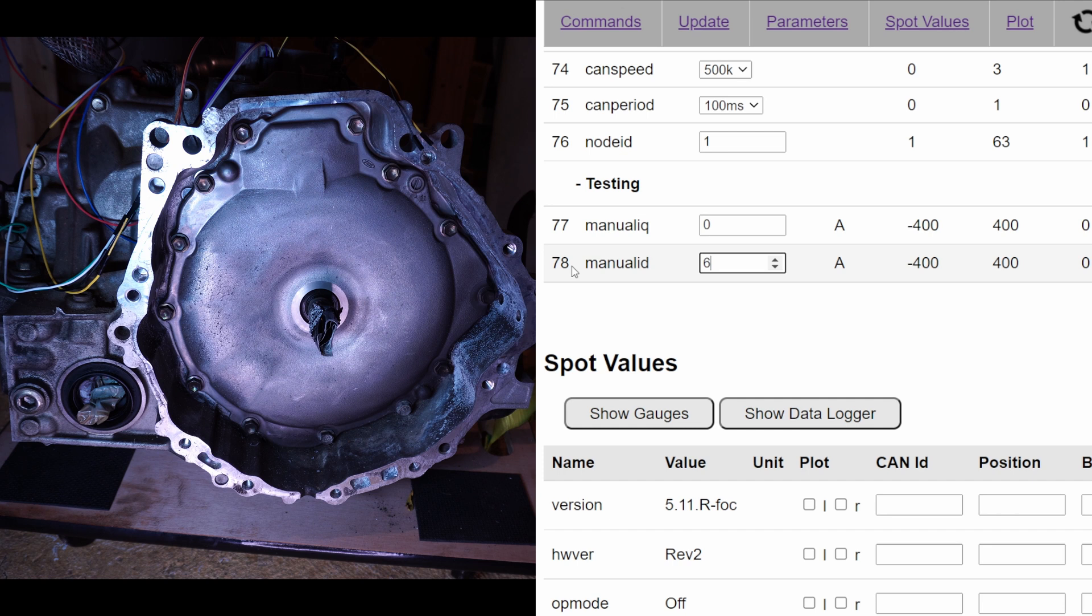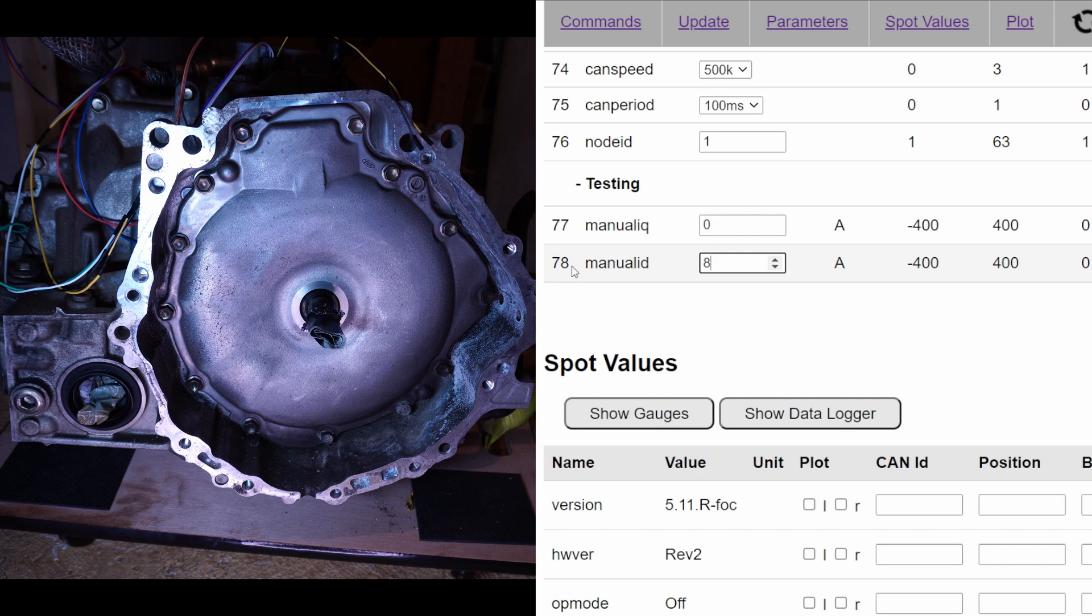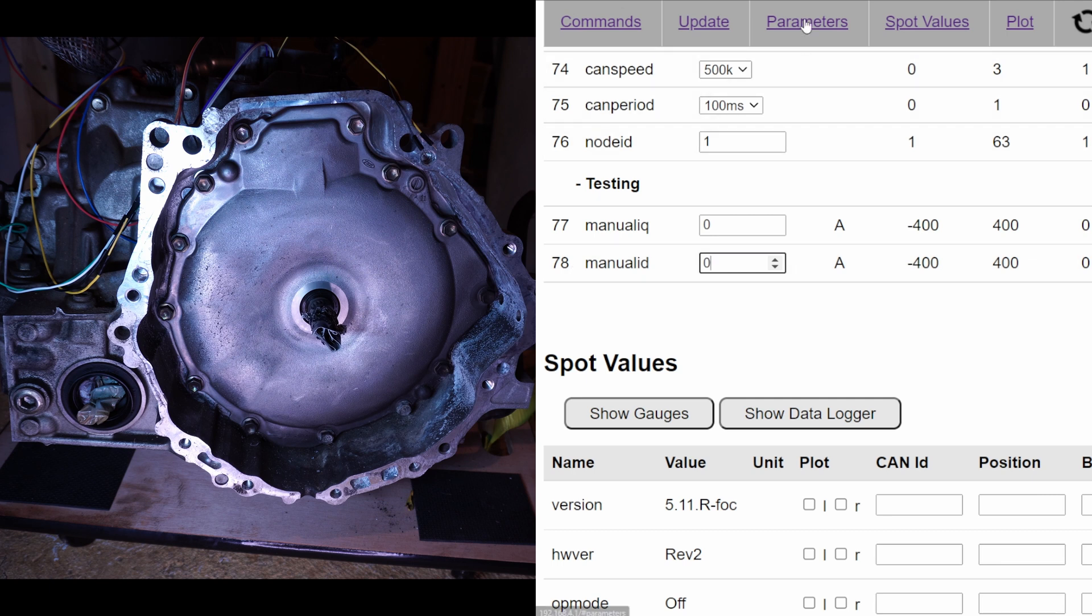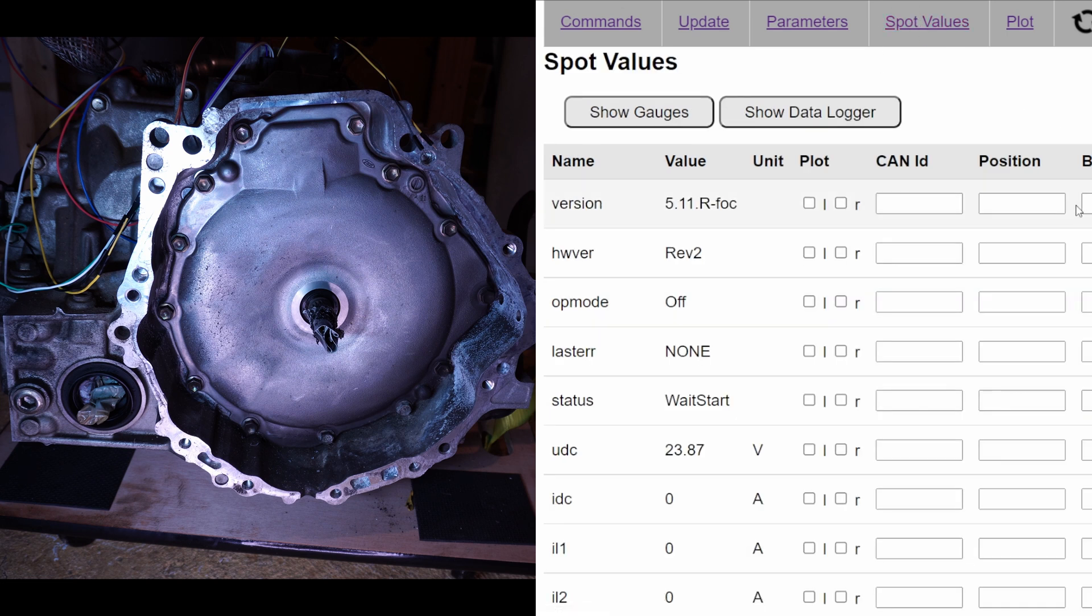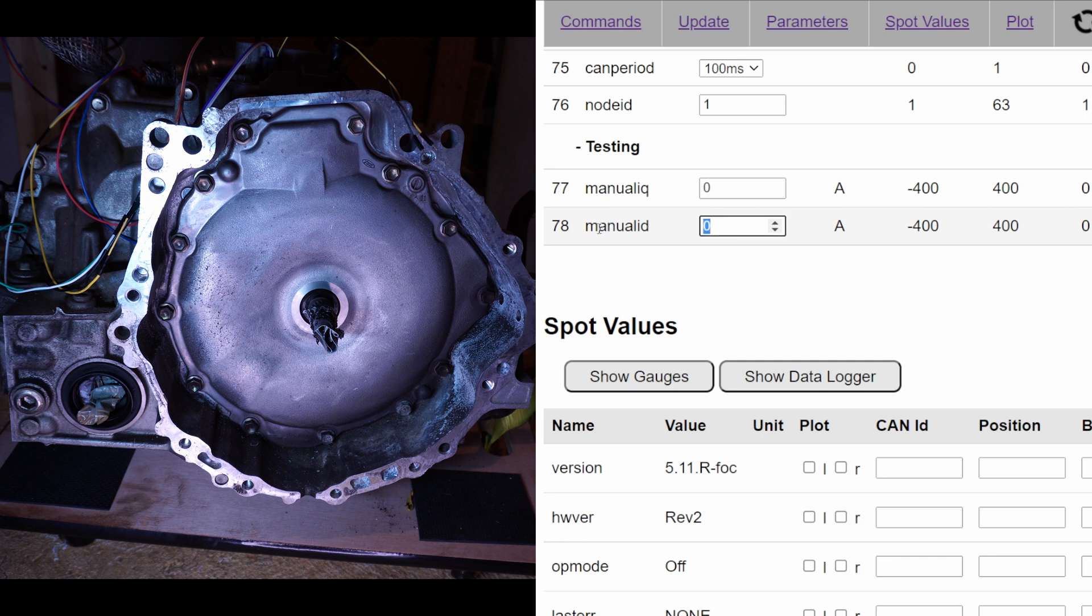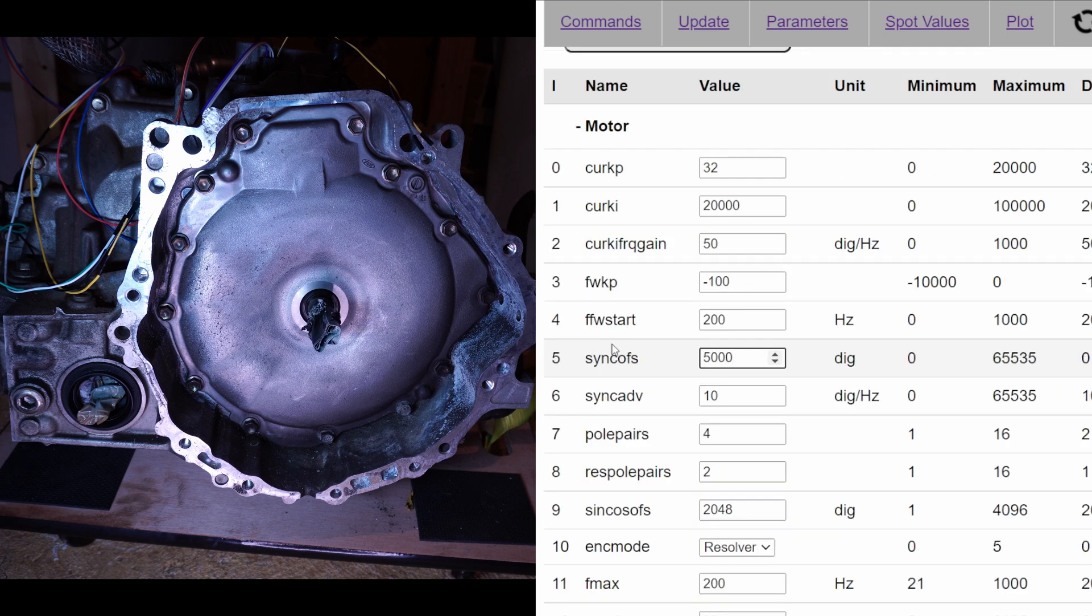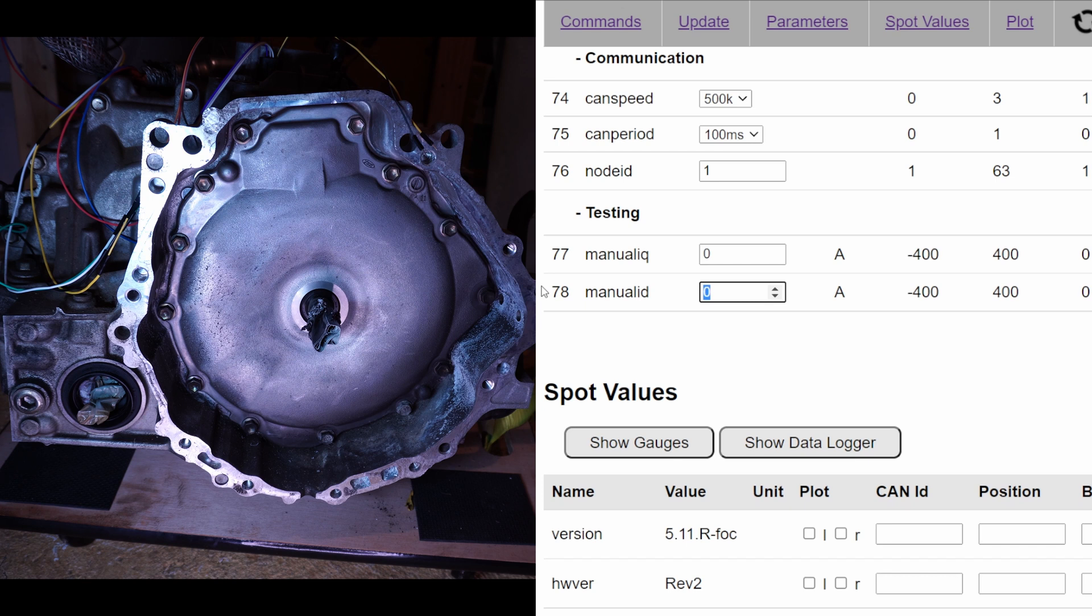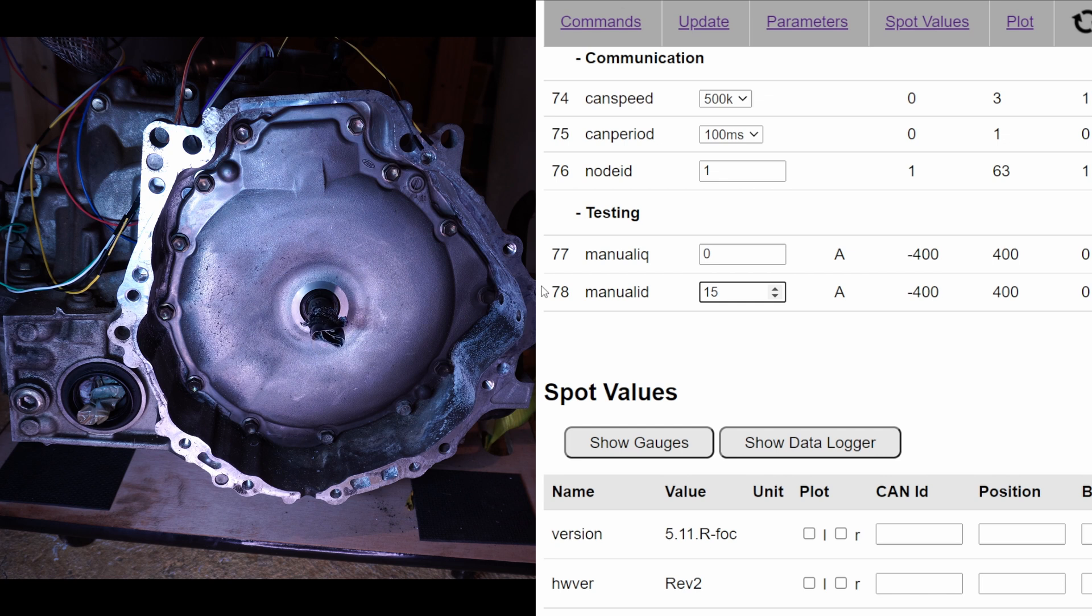Manual ID 6, manual ID 7, manual ID 8, and now it's beginning to turn. So now we have to go up to manual ID 8 to be able to get our motor turning. Back to 0. Now I'm going to go to spot values. Start with manual ID 8. Still have motion. Back to 0. Now we're going back to manual ID 10. There is no motion. For 15 we have motion. We are getting close to our expected value.